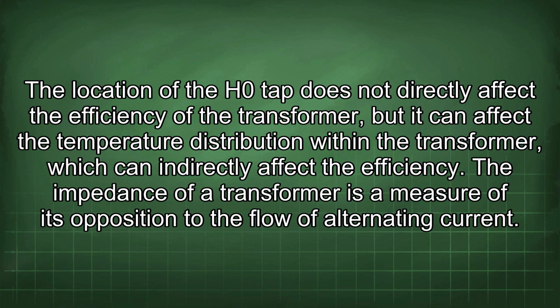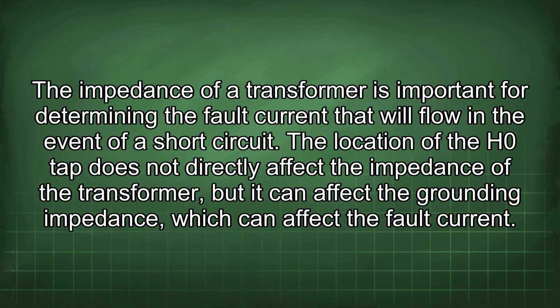The impedance of a transformer is a measure of its opposition to the flow of alternating current. The impedance of a transformer is important for determining the fault current that will flow in the event of a short circuit. The location of the H0 tap does not directly affect the impedance of the transformer, but it can affect the grounding impedance, which can affect the fault current.